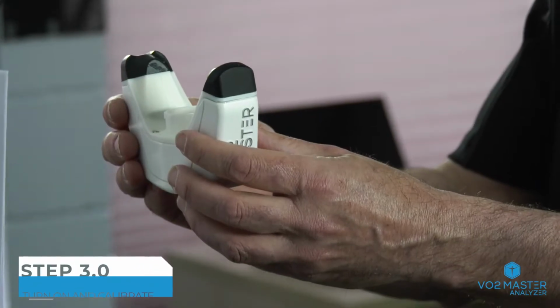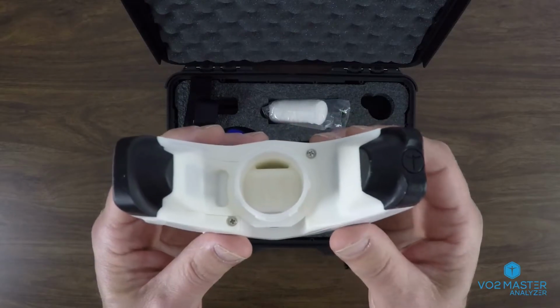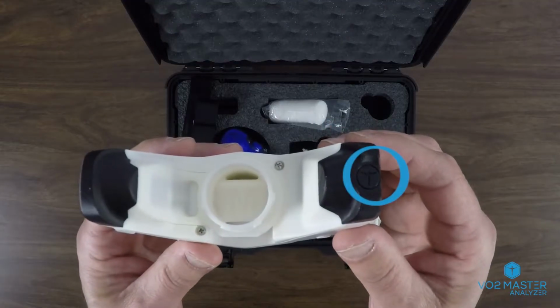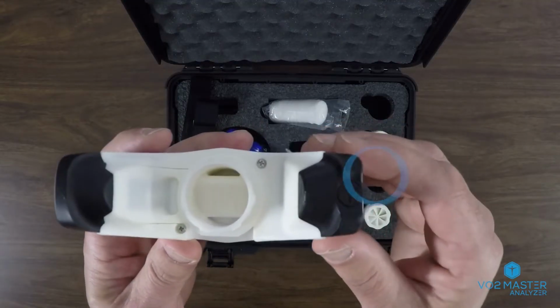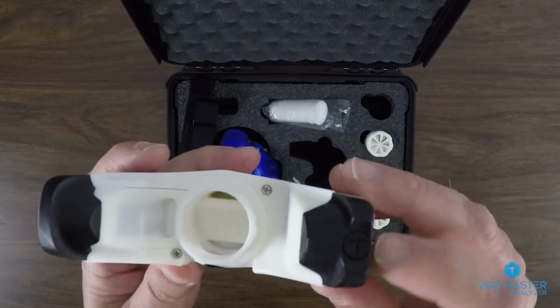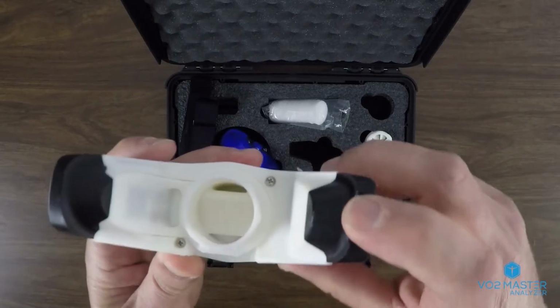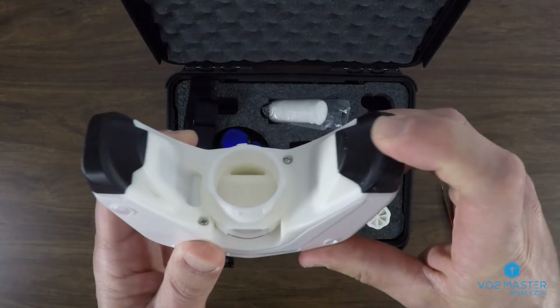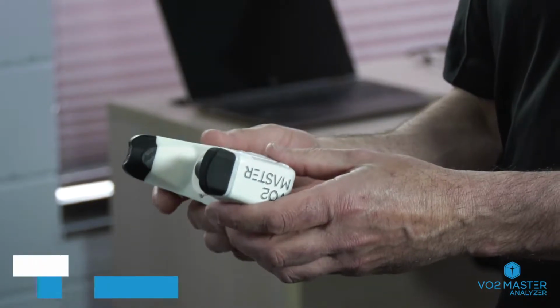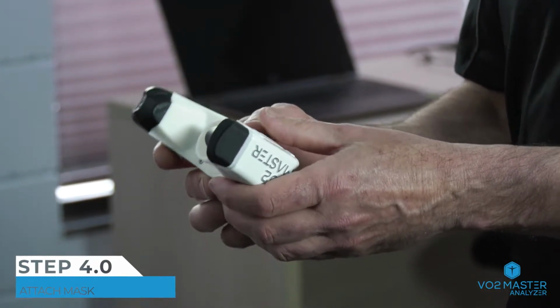But first, let's turn the analyzer on. To turn the analyzer on, simply push the logo located on the black bumper. It's important to wait 10 seconds before moving the analyzer. This is allowing it to zero calibrate. With the analyzer on and 0 point calibrated, let's install it onto the mask.